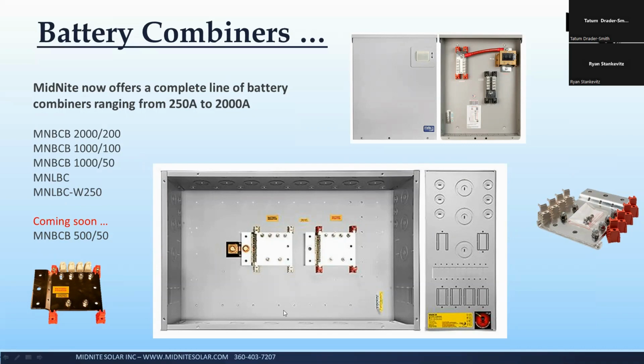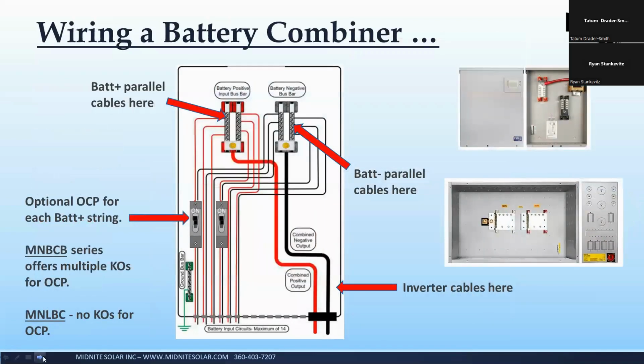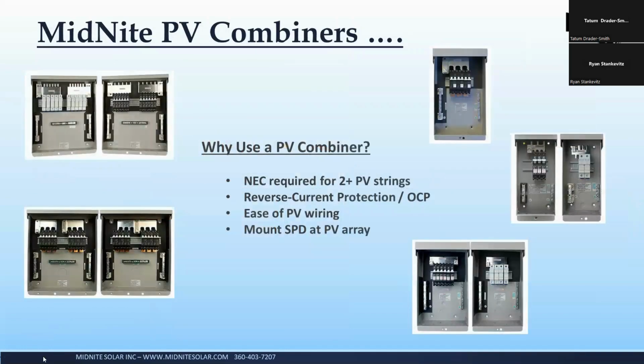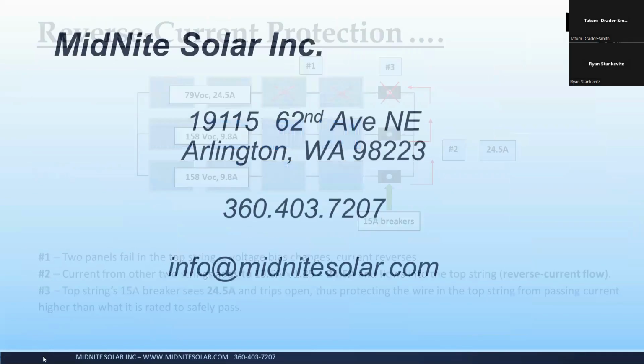So we have a whole line of battery combiners now to make it much easier to install these large systems. That's something I'm really excited about, because that 500 amp one really fits a need in the industry, in my opinion. And they all have locations for circuit breakers. So if you're doing lithium batteries and you want a breaker on each string of lithium, or if you've got multiple inverters, you can put breakers in here. So it's just a very versatile, cool box. And that's showing some of the wiring of it. So that's kind of it.